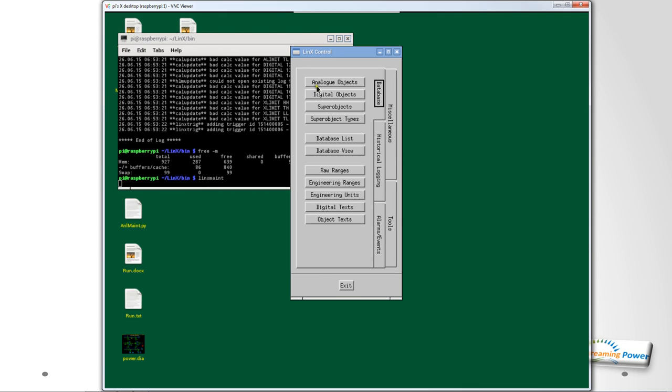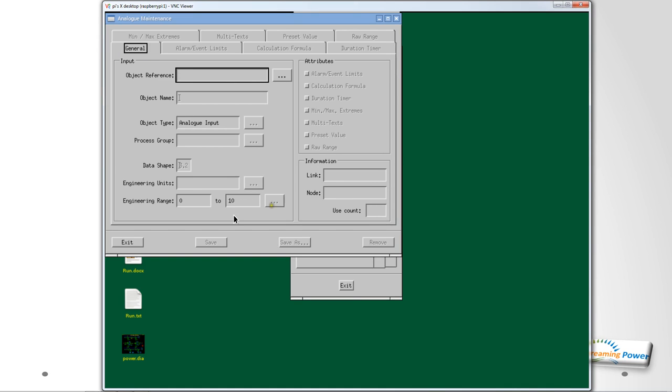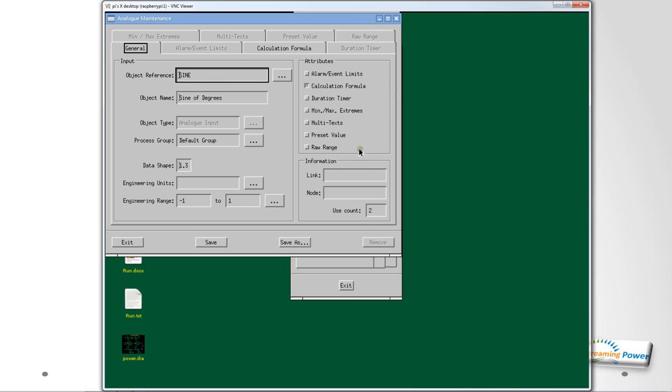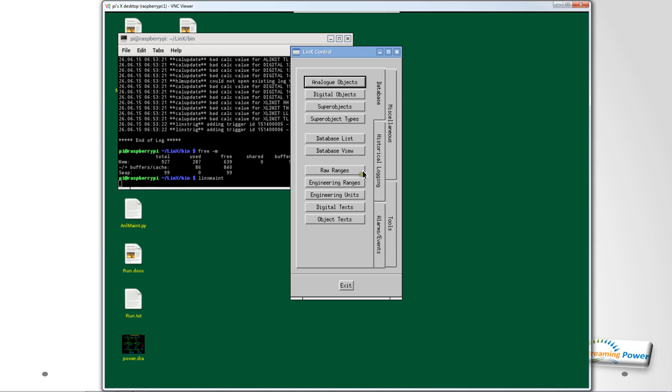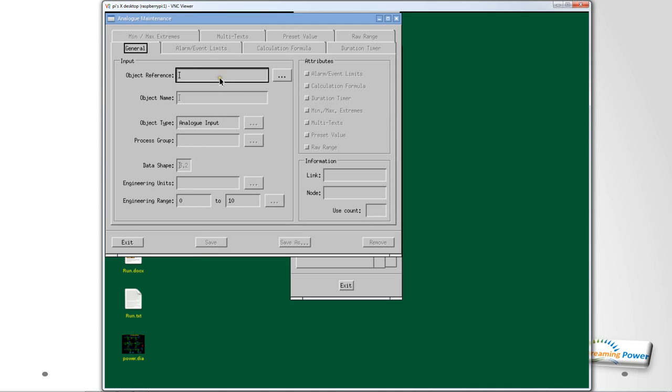When we've done that we then might want to go to the database and basically start populating the database with some signals. So let's actually do that now on the fly. If I go to Analog Objects for example, I get two parts to the screen. One is a part that is the general description and must be filled in for all objects, and then you've got different attributes that need to be filled in depending on what this is going to do. If I've already got a value in the database I can actually retrieve it and get its previous definition and of course I can modify it and I can do that online without recompiling or doing any software. This one called sine was actually a calculated value and if I go to the calculated formula it simply takes radians and multiplies the radians by sine.